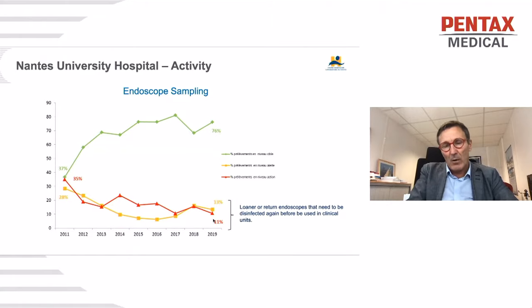At the same time, we decreased the unconform sample rate. You can see that 24% of our samples are not conform, but that concerns only loaner or return endoscopes that need to be disinfected again before being used in clinical units. That means that the endoscopes routinely used in different clinical units are almost always conform.